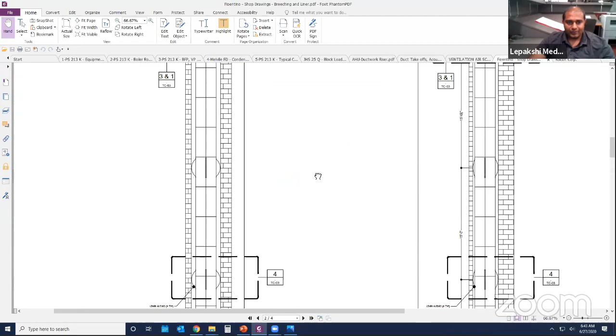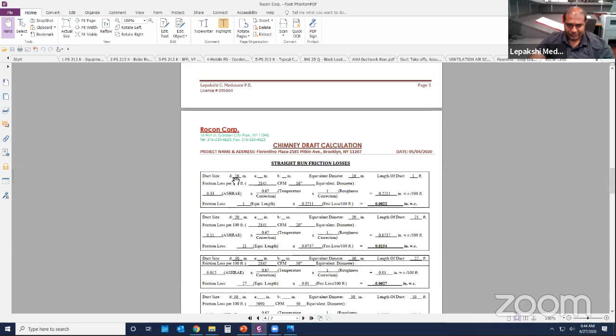you have over here this breeching on the chimney, right? So there will be friction losses of all that stuff. Now you have to calculate the friction losses of the flue gases that flew through all these things. You have the fittings over here, you have the straight length of duct and all that stuff. This is how you're going to calculate. So you come up with the straight length, the size of the duct and the length of the duct.